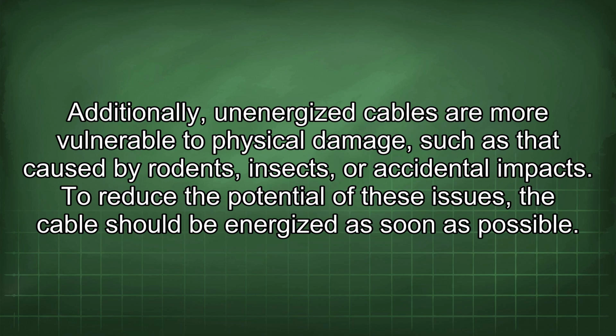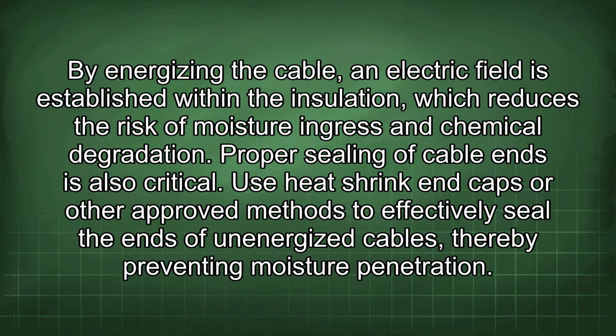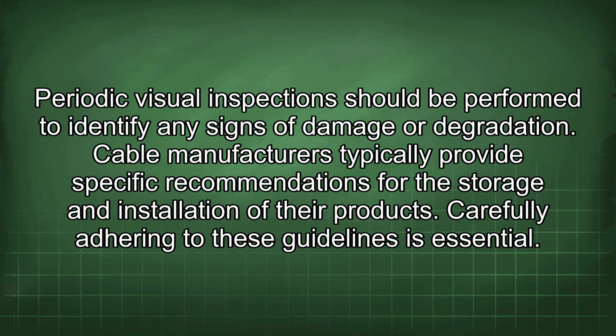To reduce the potential of these issues, the cable should be energized as soon as possible. By energizing the cable, an electric field is established within the insulation, which reduces the risk of moisture ingress and chemical degradation. Proper sealing of cable ends is also critical. Use heat shrink end caps or other approved methods to effectively seal the end of unenergized cables, thereby preventing moisture penetration. Periodic visual inspections should be performed to identify any signs of damage or degradation. Cable manufacturers typically provide specific recommendations for the storage and installation of their products. Carefully adhering to these guidelines is essential.